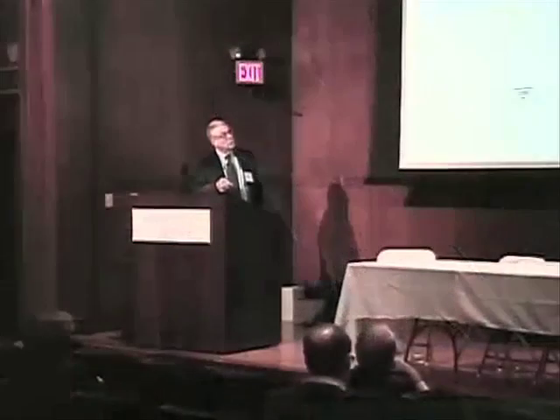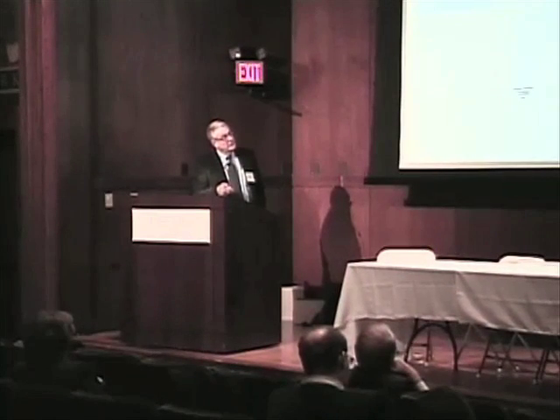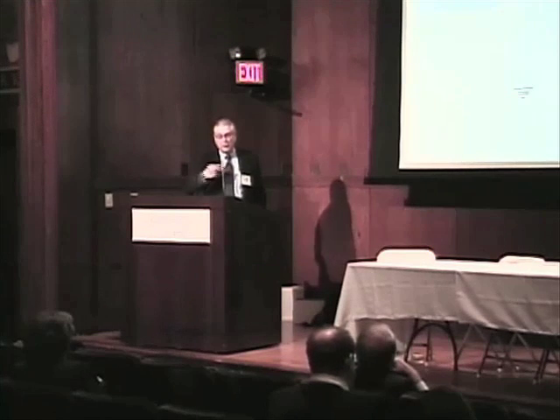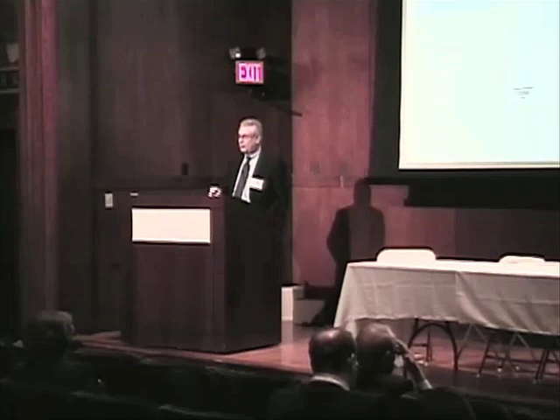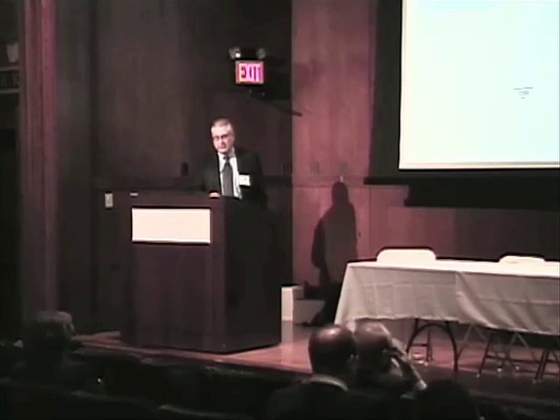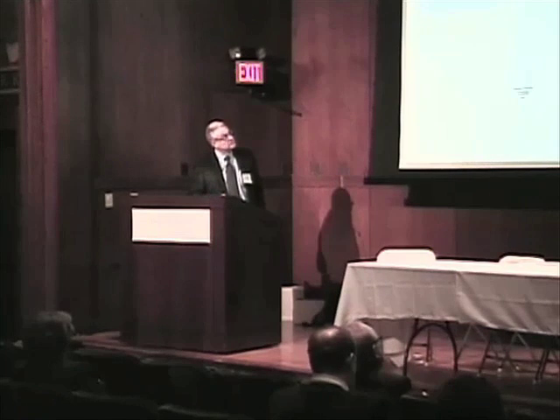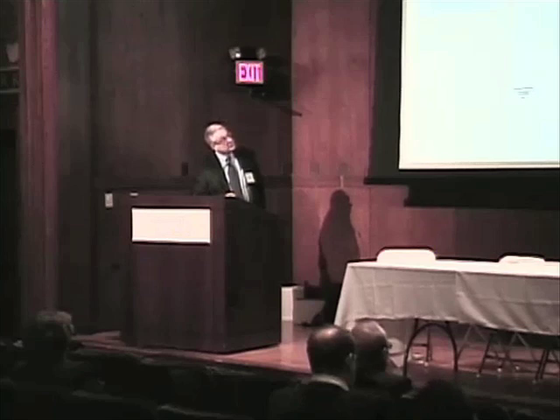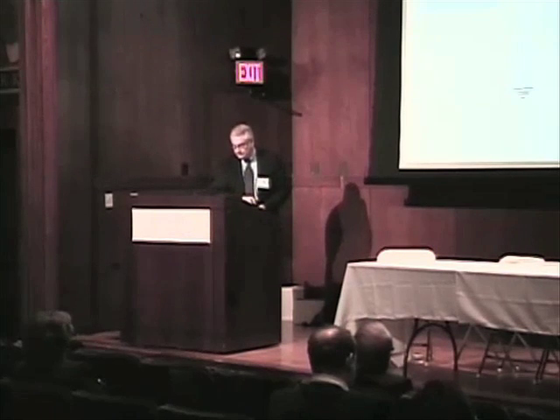Now in the very unlikely case that while we're in the protection mode, we have a ground fault, we have a surge arrester. And so if we happen to have a ground fault while we're in the protective mode, the surge arrester takes the first hit, goes into the so-called pressure relief mode. We detect that with that current, and we reclose the switches. So now we're just back in the unprotected mode, but we're still in operation. So the transformer should always be grounded. So that's kind of a simple explanation of how this works.